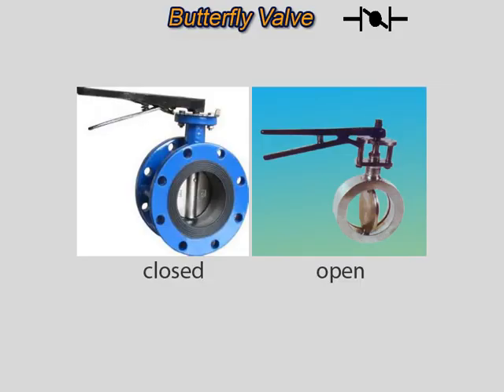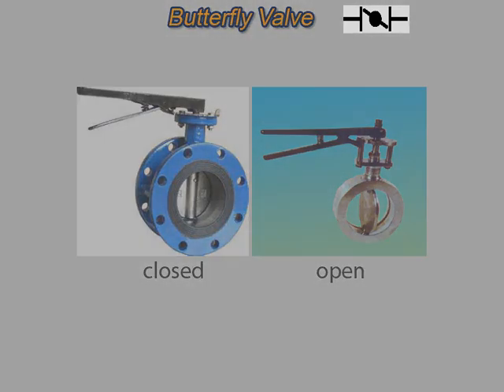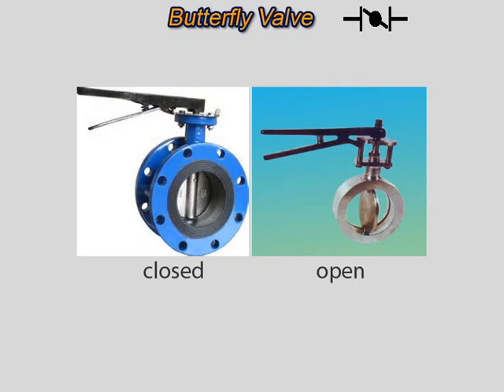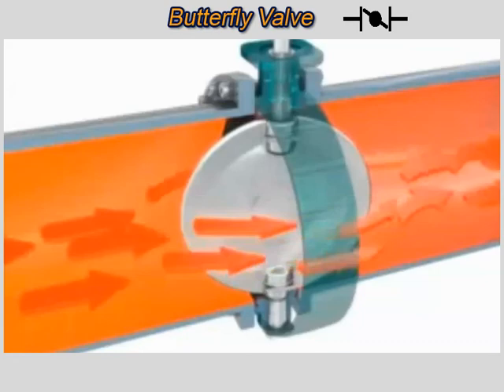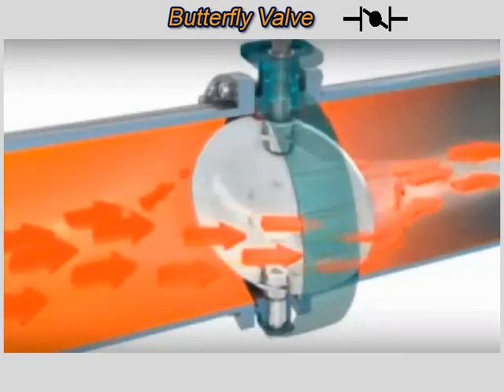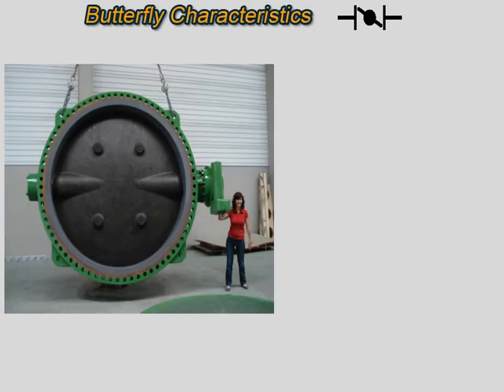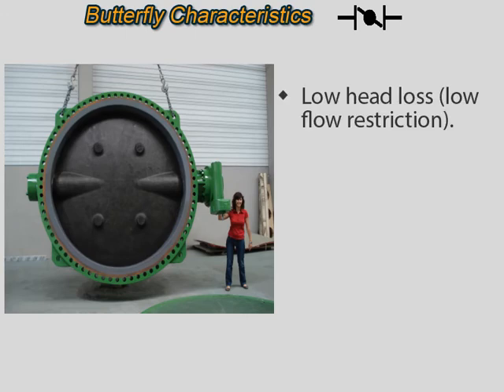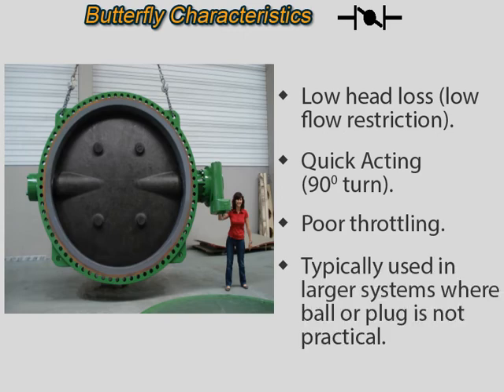A butterfly valve is a rotary motion valve that can be used to isolate flow. Butterfly valves are easily and quickly operated because a 90-degree rotation of the handle moves the disc from fully closed to fully open. Larger butterfly valves are actuated by handwheels connected to their stems through gears that provide mechanical advantage at the expense of speed. The main advantages are very little flow restriction when open and positive flow isolation with low torque. In smaller sizes, butterfly valves are also quick-acting — a quarter-turn on-off operation. Unlike ball valves and plug valves, butterfly valves can be designed in much larger sizes.